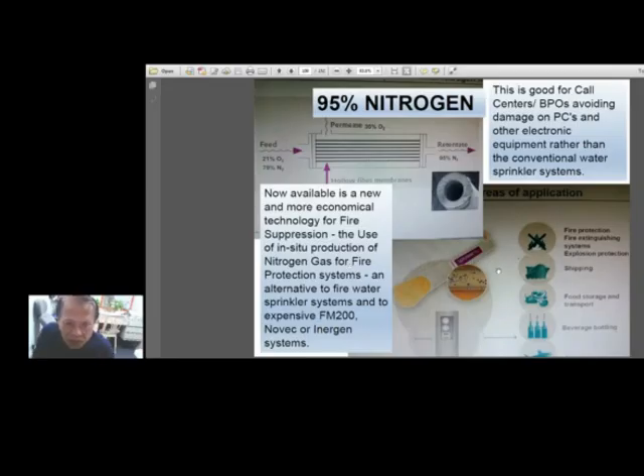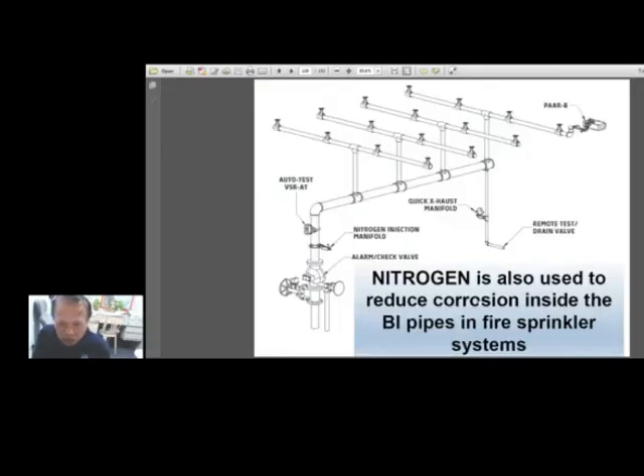What this slide is mentioning is you can have this equipment that now operates so that it will produce 95% nitrogen, just simply getting it from the air. See, the feed is 21% oxygen, 79% nitrogen. Okay, so this is good for call centers, business process outsourcing, avoiding damage on PCs and other electronic equipment rather than the conventional water sprinkler system. Okay. So nitrogen is also used to reduce corrosion inside pipes. So that is when you inject nitrogen inside your hydraulic system.